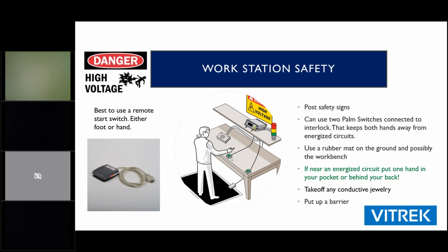You can use palm switches, a remote start switch. Basically, you can put a switch like this in. It goes to the back of that HIPOT, and the HIPOT won't start unless it sees this closed. So the intention is that if you put your hand there, 3-4 feet away from your device under test in your high voltages, good chance you won't be able to get onto that high voltage circuit. If you want to be even more safe, you can put 2 of these - left hand on that one, right hand on that one, and now you know both hands are safe.